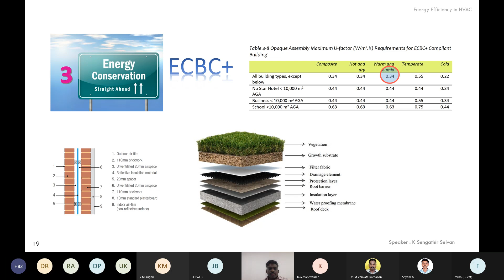In order to achieve that, we can have some kind of vegetation on the roof, and we can have a better insulation layer. A vegetation roof itself reduces the radiation load by 50%, and this is what ECBC recommends. So you can see a comparison: from base case 742 TR, by changing single glaze to double glaze we have brought it down to 653. Then by reducing the window wall ratio, we have reduced it to 642. But with the better roof, we have reduced it to 578.